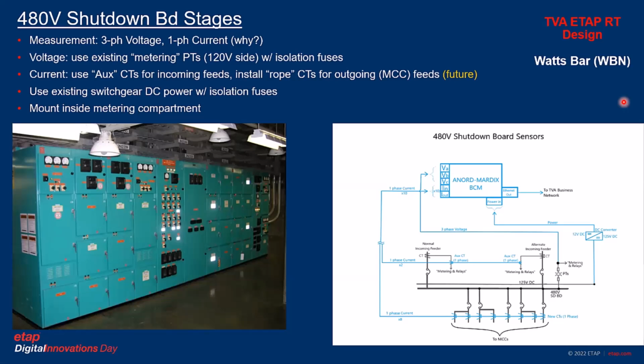Likewise, our 480 volt shutdown board stages, you can see the detail here for these branch circuit monitors. It's a very similar concept. We're going to use 3 phases of voltage, but only single phases of current. We're going to use existing metering circuits, isolation fuses, auxiliary CTs, all the same stuff we talked about before.